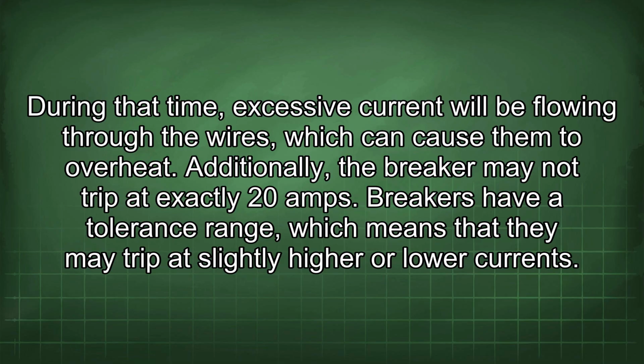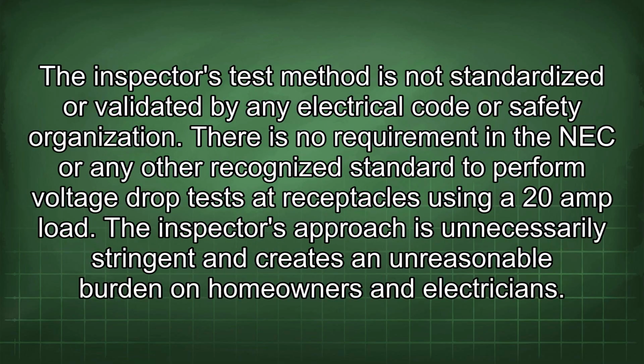Additionally, the breaker may not trip at exactly 20 amps. Breakers have a tolerance range, which means that they may trip at slightly higher or lower currents. The inspector's test method is not standardized or validated by any electrical code or safety organization. There is no requirement in the NEC or any other recognized standard to perform voltage drop tests at receptacles using a 20 amp load. The inspector's approach is unnecessarily stringent and creates an unreasonable burden on homeowners and electricians.